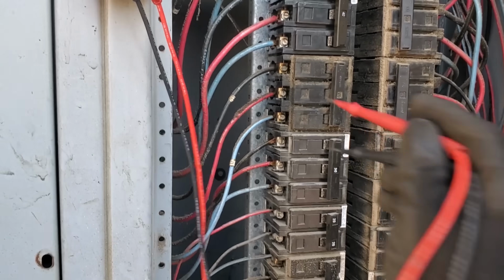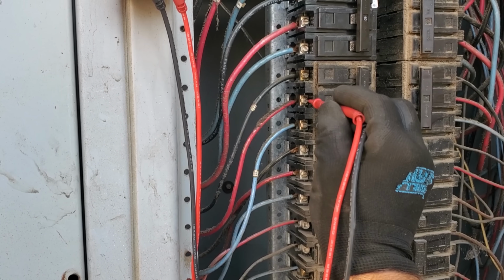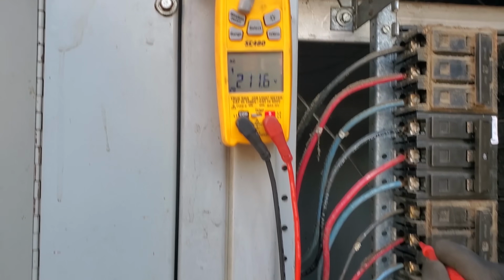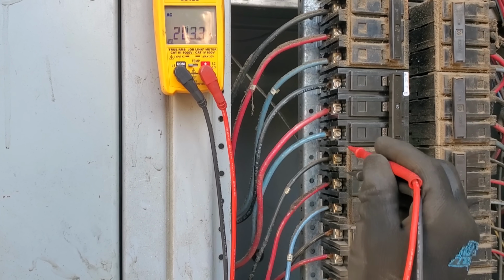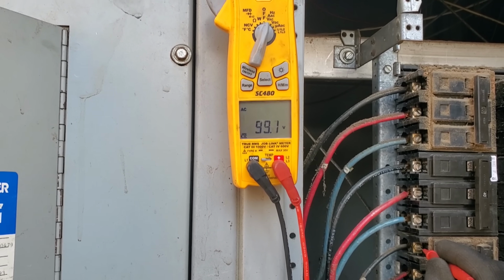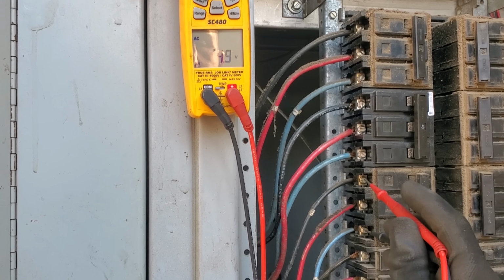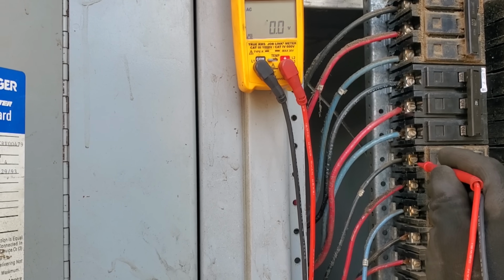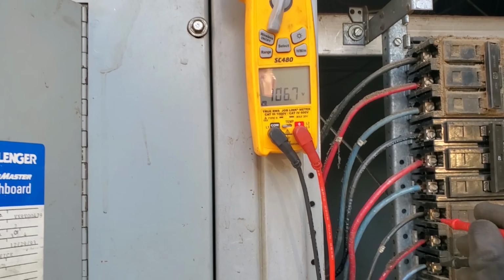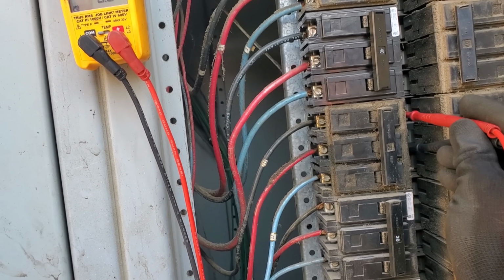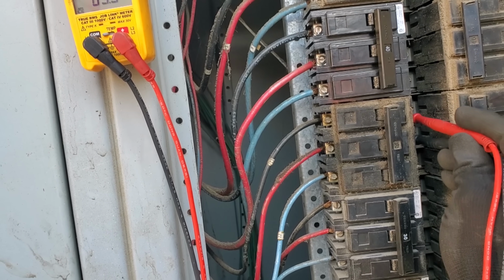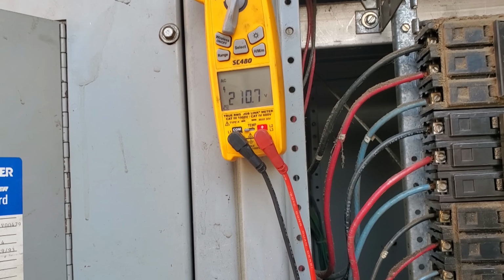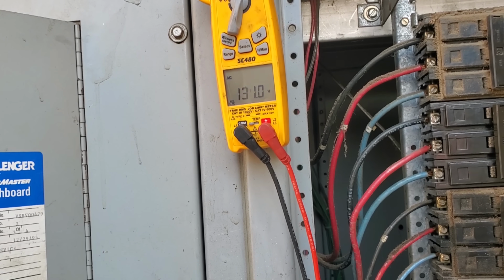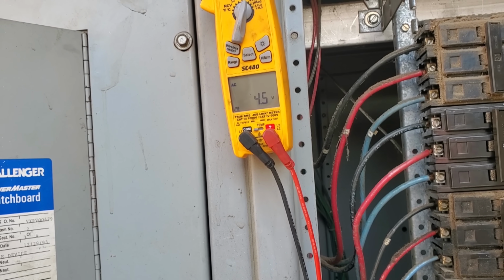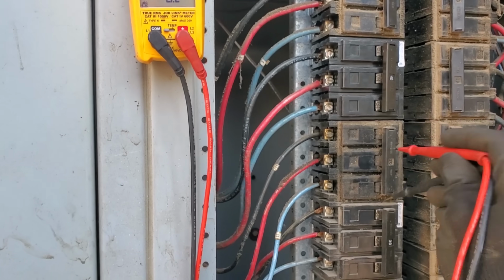All right, here's what we got going on. It is this breaker. So 211, phase B to C. Phase A to B, we've got 99 volts. And phase A to C, we have 106. And then if you go to the bus bar right here, you got proper voltage, proper voltage, proper voltage. So the problem is the breaker.